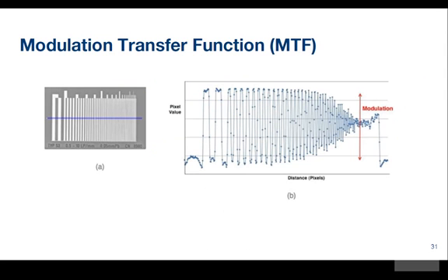So this shows what happens if we image this phantom. It would be made of material that is embedded, highly absorbing and less absorbing, so typically it would be blocks or slices of lead and plastic, in this case of decreasing thicknesses. So the number of line pairs per unit length is increasing, and then we take a profile through, and you can see here.